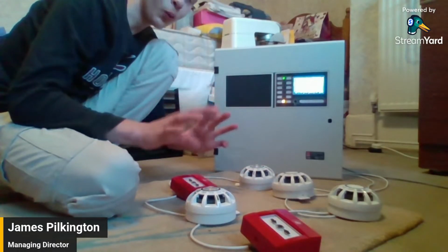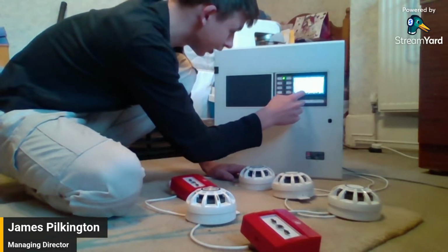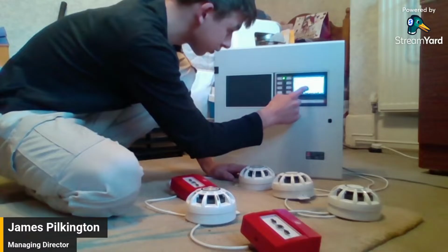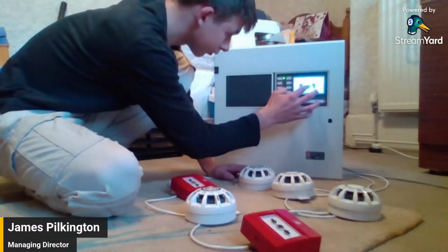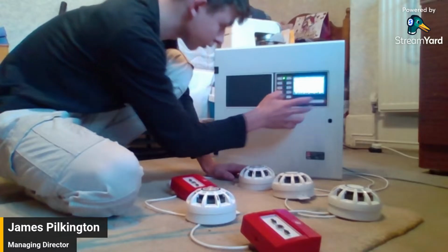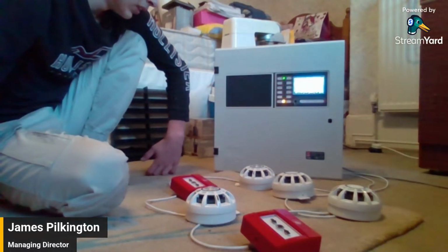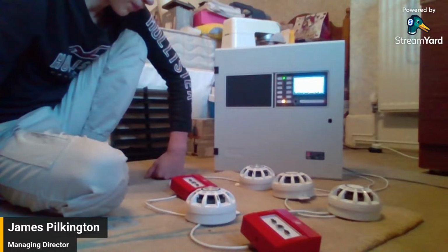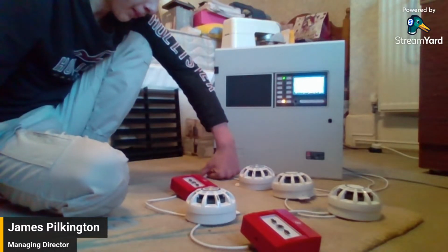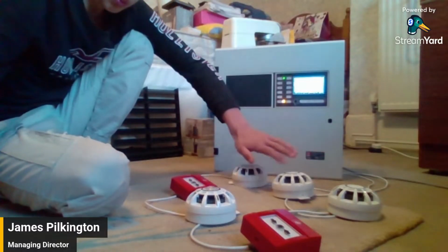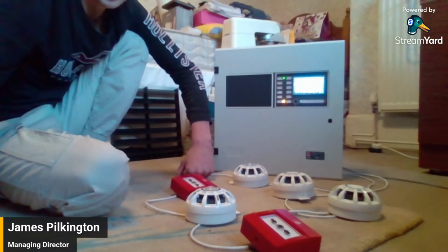I had this all working earlier. I was not prepared for any problems. Let's try and relearn it. Try and relearn it and see whether we can get anything different. Hopefully it might auto address this loop a bit differently. Now I've reseated the detector heads. If not, we're on a fault finding mission.